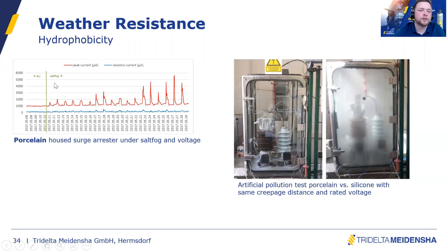And then we switch on salt fog, the salt fog artificial pollution test. And each time the salt fog is switched on, the surface current is rising. So it's not the leakage current through the zinc oxide block, it's the surface current that is spiking up here. And actually those spikes are increasing. So if we had proceeded with this test, we would see a very strong upwards trend of this surface current.